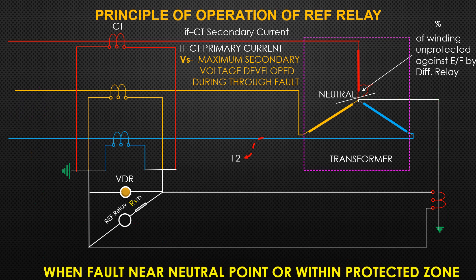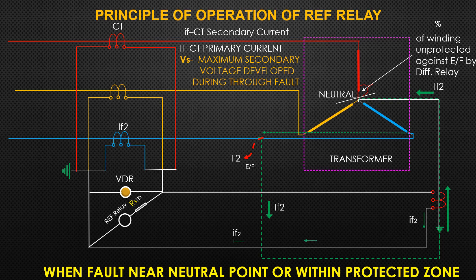During an inside fault, the secondary currents of the two CTs have no other way to go than through the relay. The voltage dependent resistor (VDR or varistor) is used to protect the CTs and windings by limiting voltage during heavy inside faults. The resistance of the secondary wiring connecting the CTs together should be as low as possible.